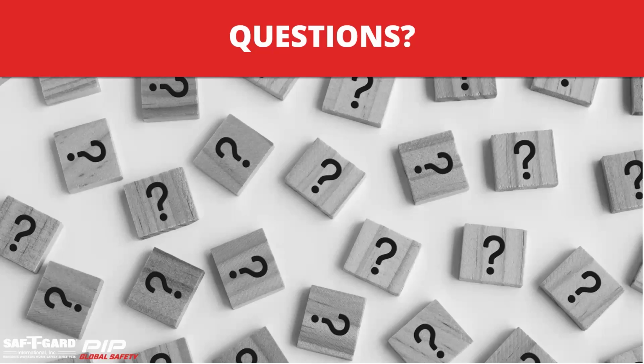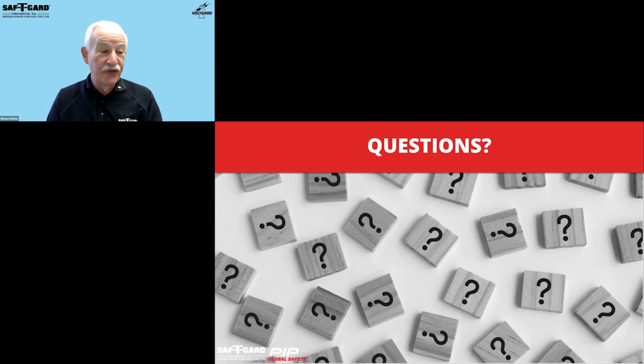Okay, perfect. What additional PPE is used or needed for arc flash and industrial electrical safety, and does Saf-T-Gard carry those items? Second question is easy. That's yes. The first question is going to depend on an arc flash hazard analysis, which will determine if 8 cal daily wear is enough, an arc flash face shield, or a complete hood or a complete coverall. So there's no easy answer to the first part of that question. It's going to depend on what that arc flash hazard analysis is of the particular facility. Okay.